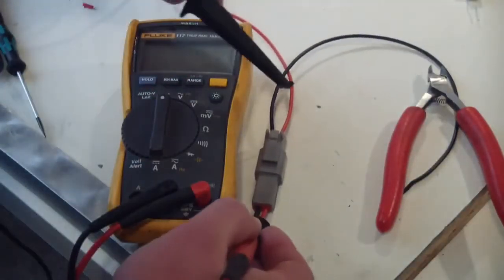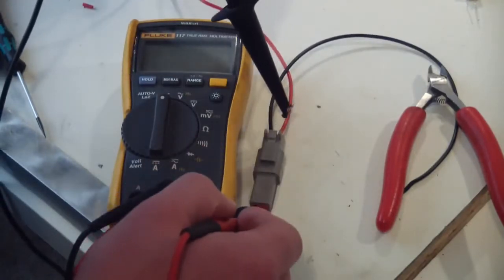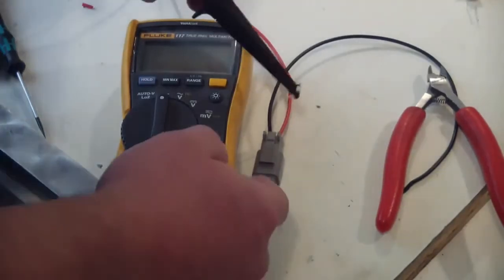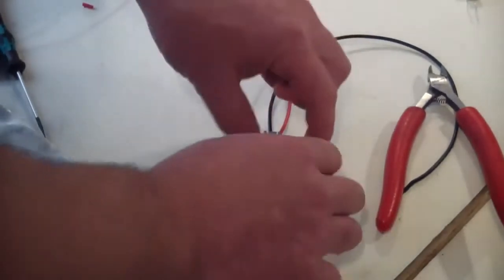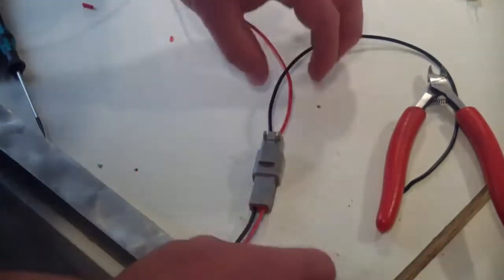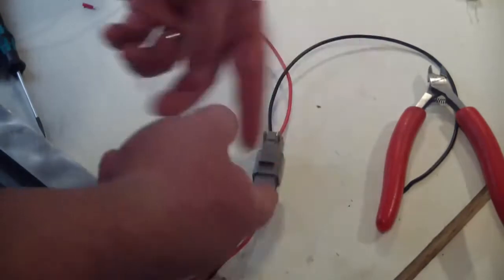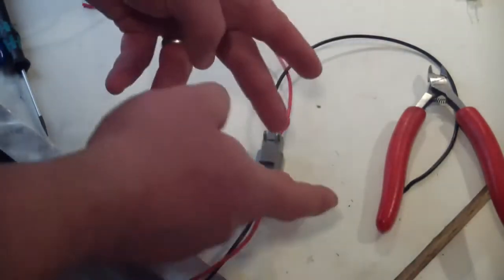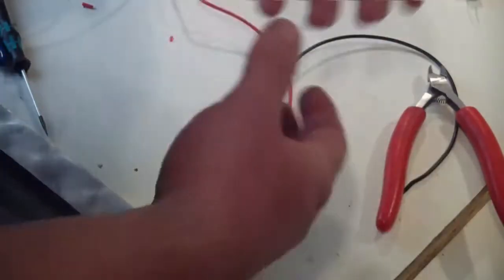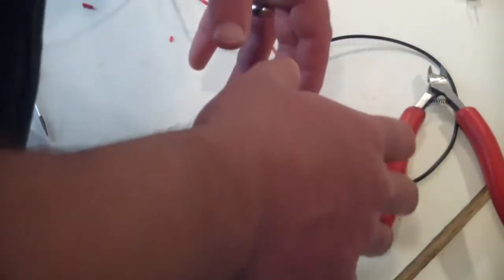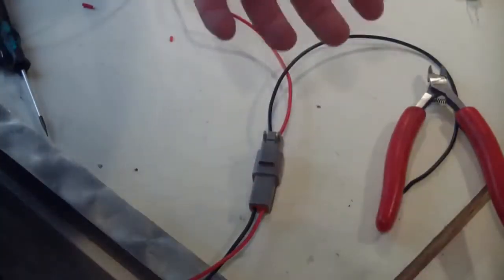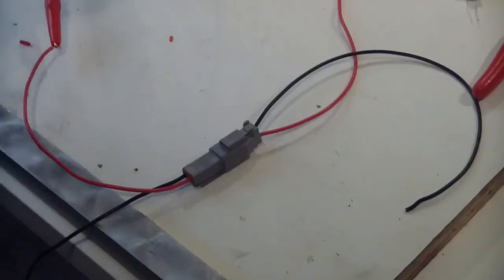And then you're going to have to go in there a couple months later and rewire the whole works. Now not to judge. I mean, we've all done it. It's not right. And hopefully you'll learn from other people's mistakes because when you pierce the insulation, you've just given a death sentence to that wire. Just so you know, the creeping green death will get it eventually. Anyway, I digress. I know this is a bad connection. I'm going to power this up and we're going to take a shot with the IR. And of course, if you're checking just for power, you open this up, you test to see if you got power there. Of course, there's power there because now you've broken that resistance. Then when you go to put it back together, chances are it's going to work properly. Intermittent problem. Don't know what it is. Guy comes back in a month. He's got the green death. You look like an asshole.